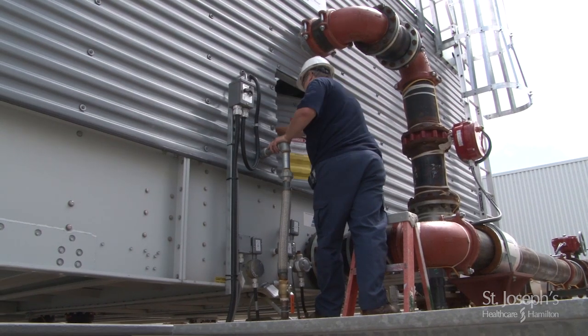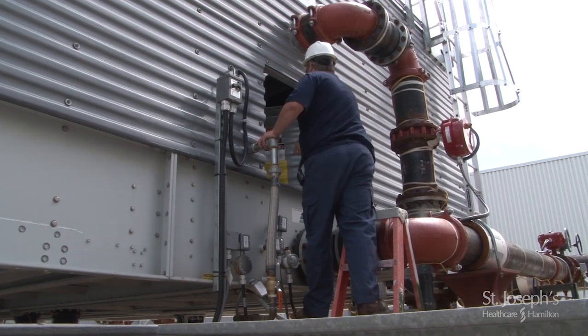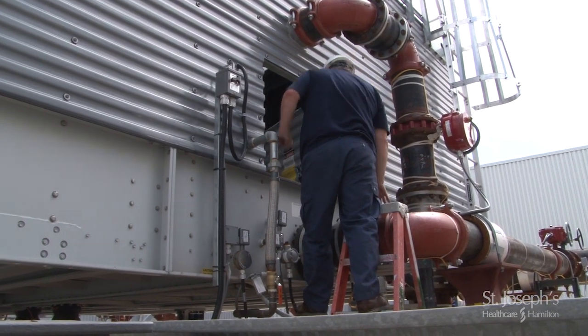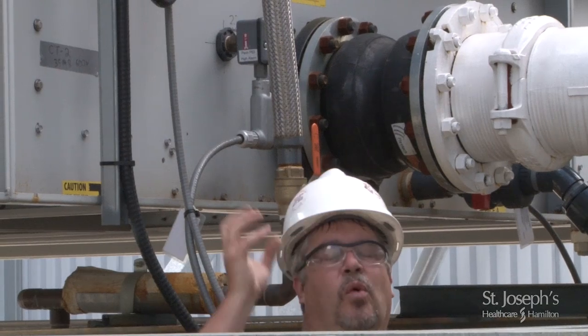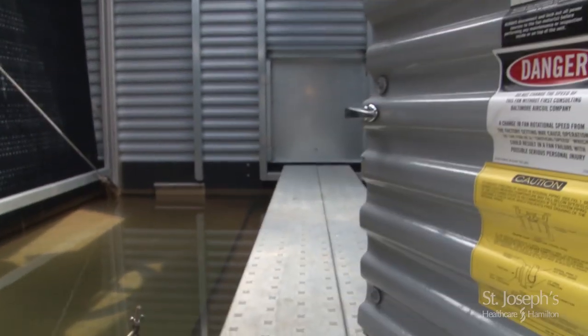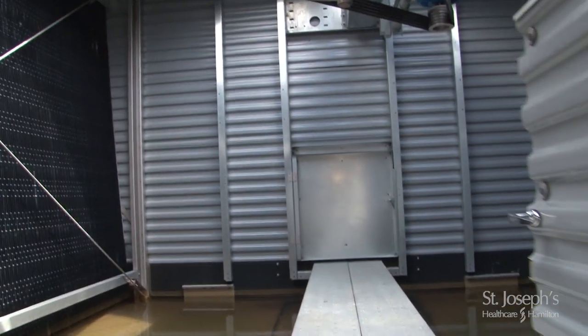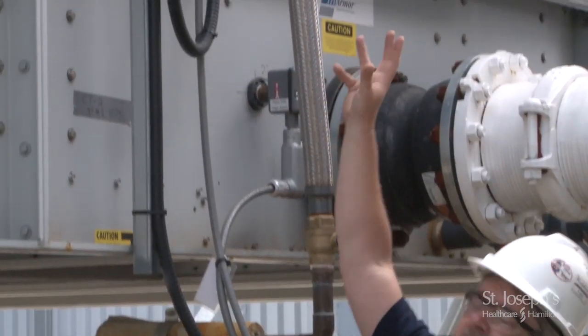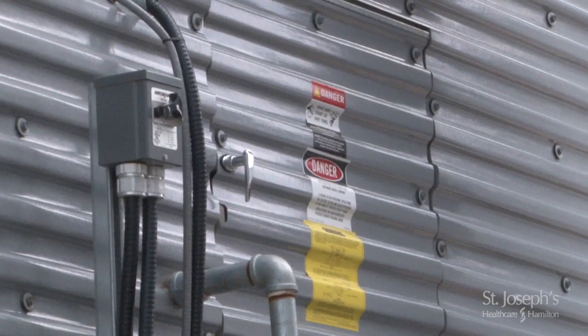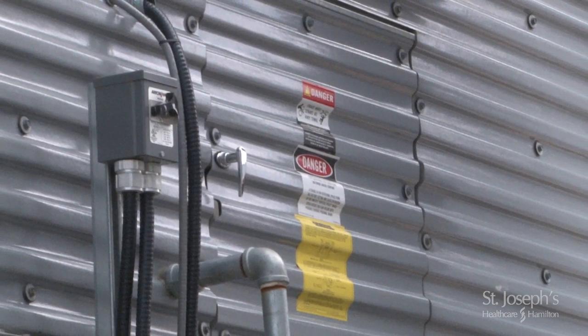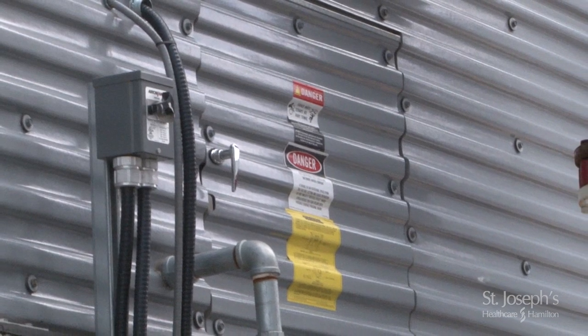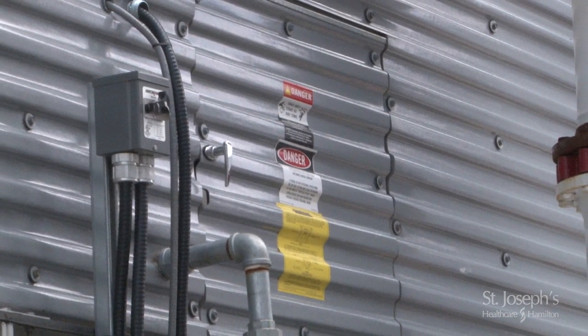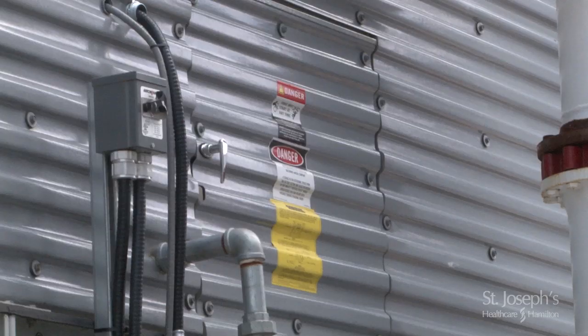If you're going in just to do regular maintenance, always go into the mechanical room first. Once you're in the mechanical room, you'll shut everything off on the VFD. Then you can come out here, and as an added feature, you can shut this one off and put your lockout tagout here. Then you know you're pretty safe. It's not going to come on while you're working in the cooling tower.